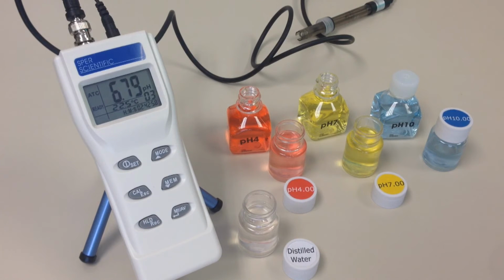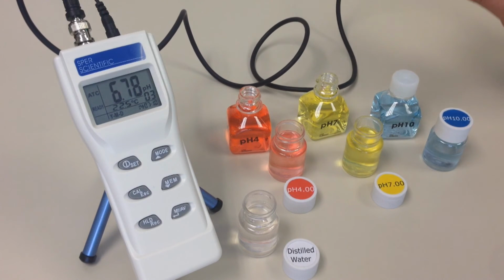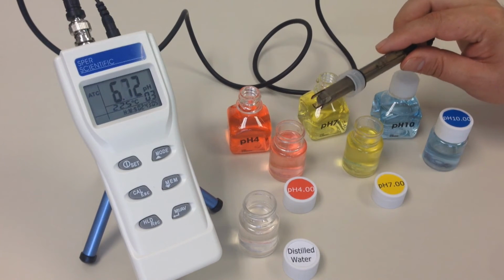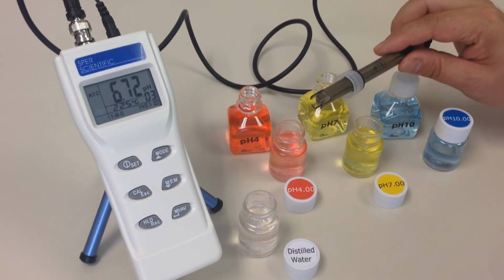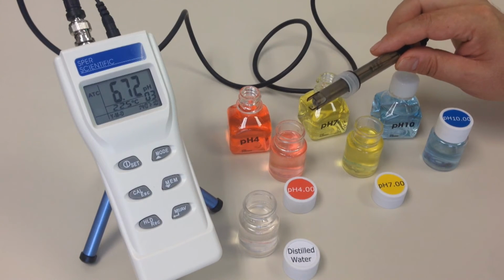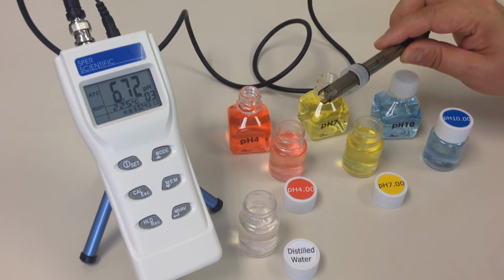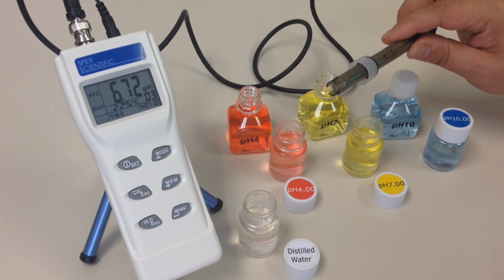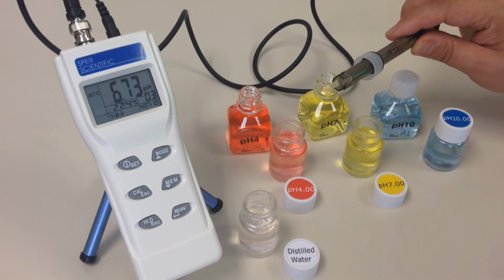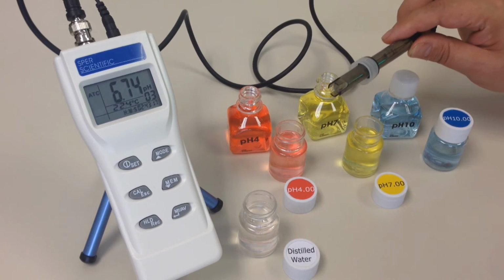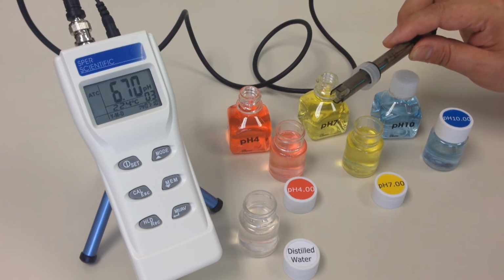Now we are ready to calibrate this meter. First thing I'm going to do is take my probe. Now I want to point out I am using a probe using ATC, or automatic temperature compensation, to do this particular calibration. If you are not using a probe with ATC, please refer to the manual on how to calibrate using that type of a probe.